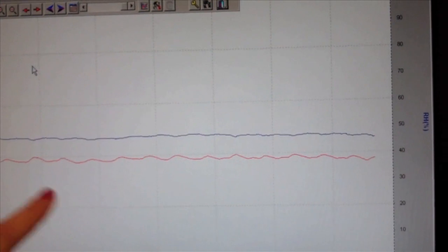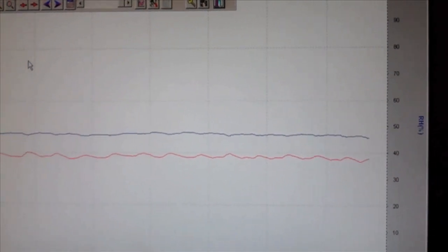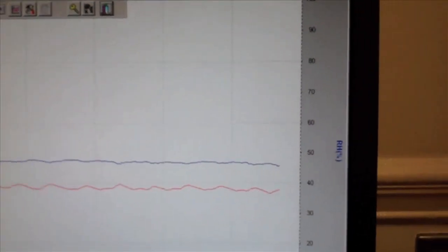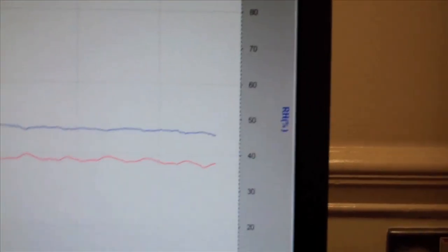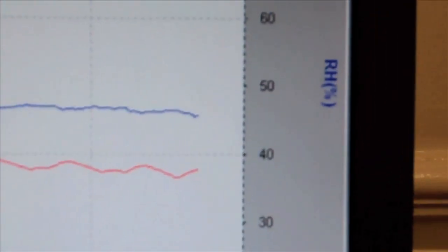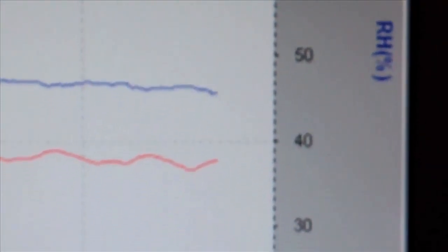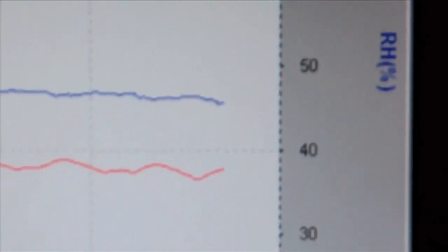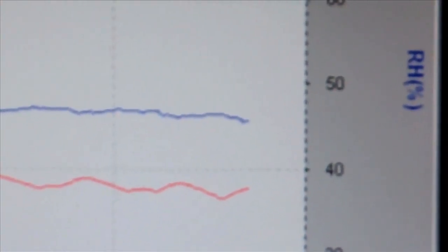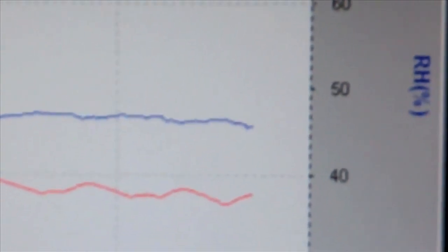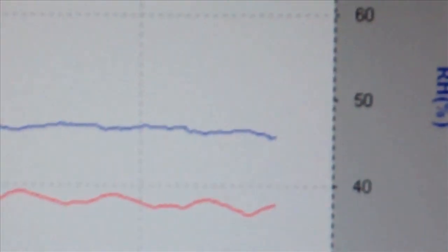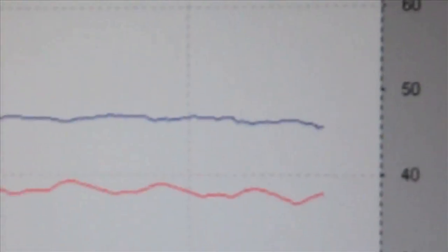As a comparison, this is a recording within a case. As you can see the temperature and relative humidity is very stable and that's what we ideally would like to have in all the galleries. Yeah, so we can see there that the relative humidity is about 45%. So the showcases are really helping to stabilize the environment for the objects.